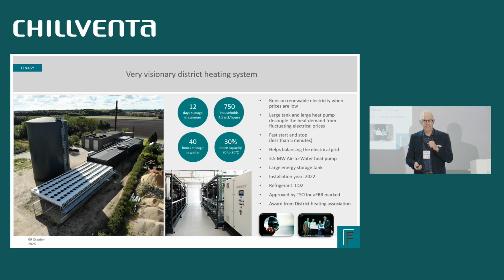The other point is temperatures in the district heating grid. For heat pumps, we need lower temperatures than what we have historically had in Europe. In Denmark, we are a little bit lucky because we have what we call fourth generation of district heating, low temperature district heating, but in many, many countries, the temperatures are too high. Especially for CO2 heat pumps, we need the return to be lower. So that's the second topic of today, lower return temperatures.